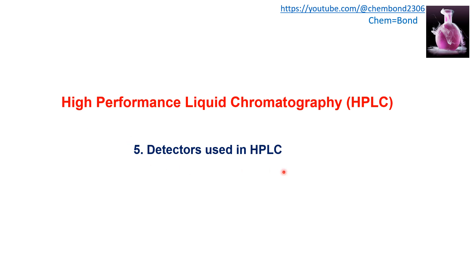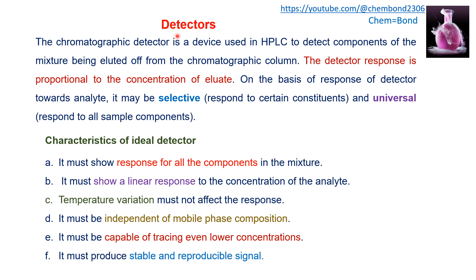One of the components of HPLC instrumentation is the detector. A chromatographic detector is a device used in HPLC to detect components of the mixture being eluted off from the chromatographic column. We inject the sample into the injector, it passes through the column, and at the end it reaches the detector. This is the most important component of HPLC instrumentation because it shows the final qualitative and quantitative results of the sample components.